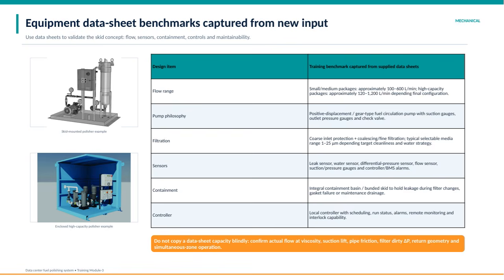Filtration includes coarse inlet protection followed by coalescing or fine filtration, with selectable media ranging from 1 to 25 microns to meet cleanliness and water removal targets. Sensors play a critical role, including leak detectors, water sensors, differential pressure sensors, flow sensors, and suction and pressure gauges. These feed into controllers or building management systems to raise alarms and ensure smooth operation.